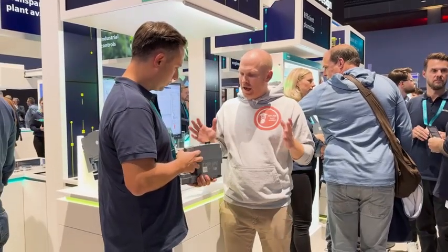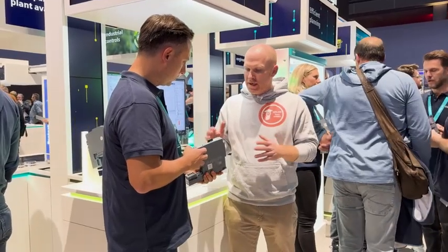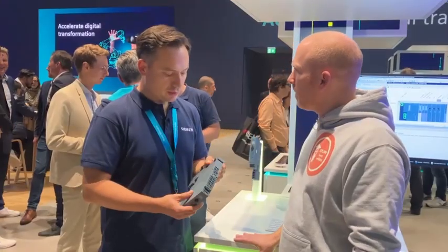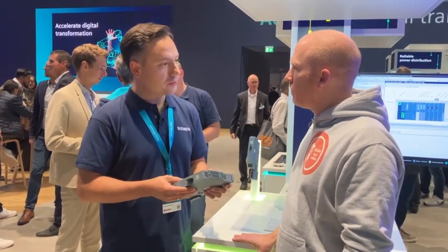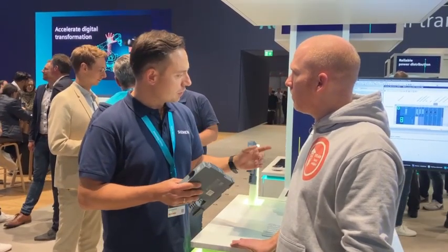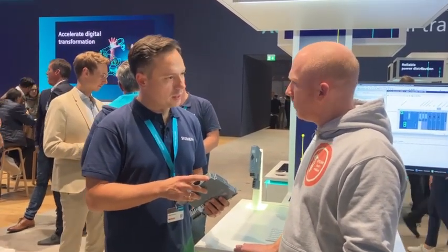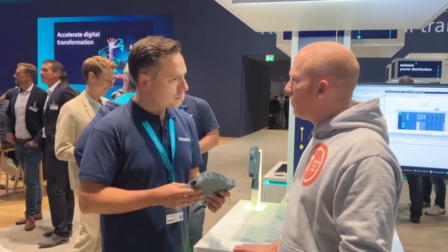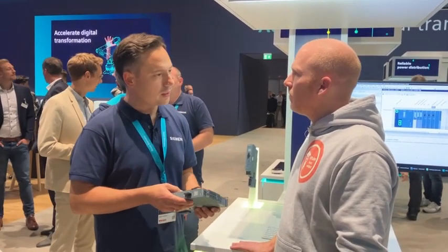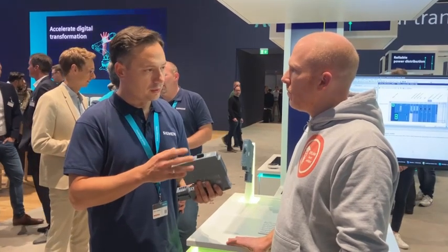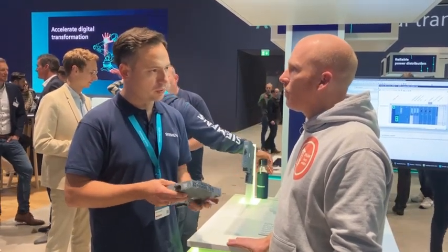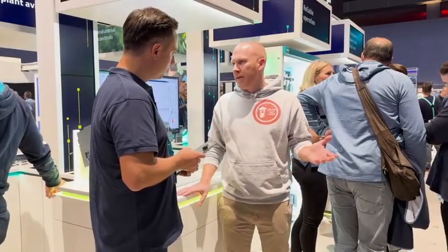Let's talk a little bit more about the hardware. In which range of current or power for motors can you deliver this? We have two current ranges actually. The first one goes from 0.1 to 2 amperes, and the second one is from 0.7 up to 7 amperes. That's around 3.5 kilowatts, depending on which motor you have. What is a typical application for this?